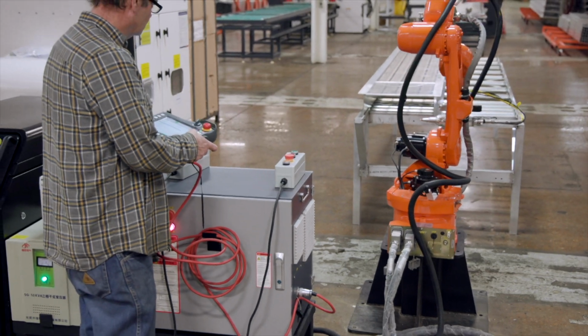A lot of electrical feeders used in the USA today are built around 2 types of technologies. One is pipe and wire, and the other one is rigid bus duct. Now, pipe and wire is a very robust system, but it's very expensive, and it takes a lot of labor to put in. Bus duct is a little more cost competitive, but it's prone to failures. Every 7 to 10 feet they have joints, and these joints break down over time and they fail. They're not waterproof, so what happens is they get wet or a sprinkler lets go inside your building and it hits your feeder, it blows up, and your entire building is down.